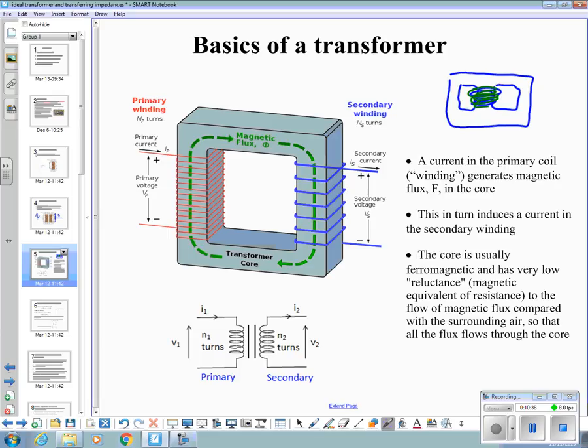The other thing that is done and you probably all know this if you looked at a transformer core is made up of laminations. So instead of just being one solid lump of iron it's made out of laminated steel plates that are insulated away from each other. And what that's to do with is to reduce the effect of what's called eddy currents. You'd get currents set up within the iron core that cause it to heat up and become a waste of energy. If you insulate the plates from each other, you're less likely the currents are going to go around rather than within it.